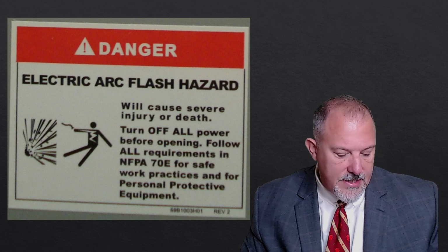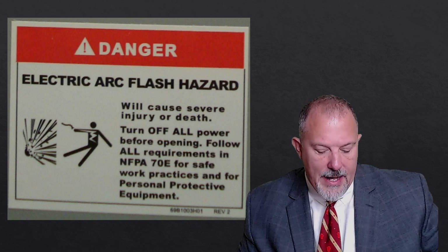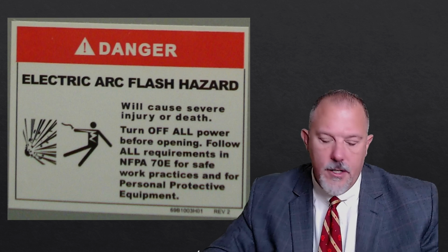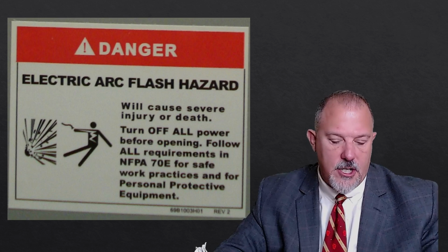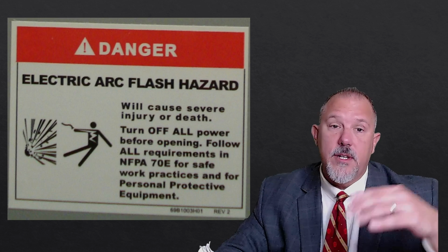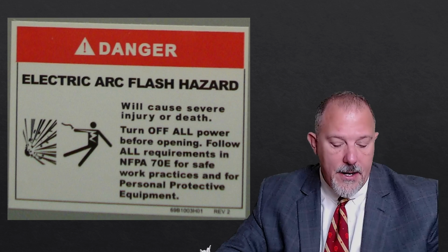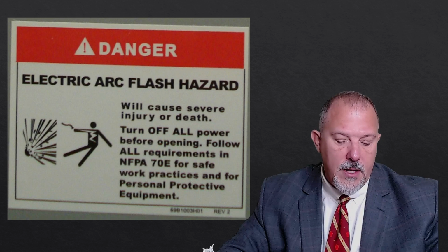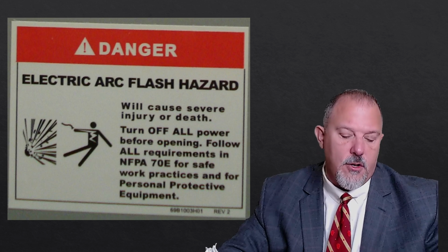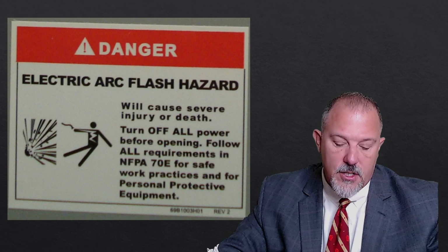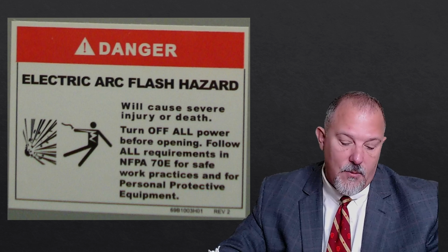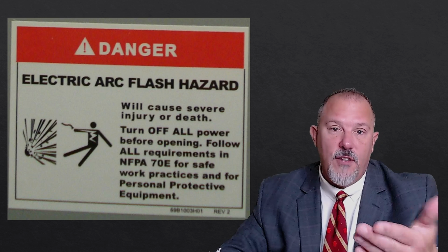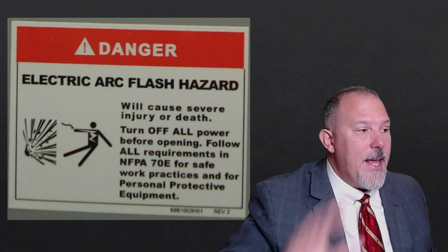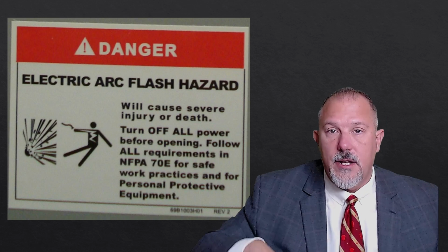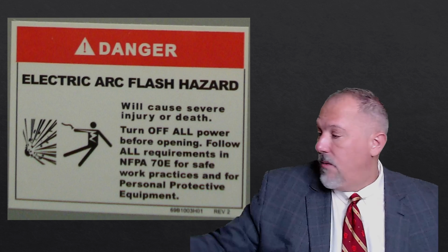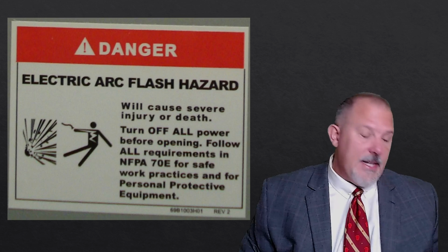So if you look at 110.16, you have an A, general requirements, which basically tells you some of the general information about how to apply that section. And B talks about service equipment. So at service equipment, you're going to be putting this label and that other label, possibly, or you're going to be putting the nominal system voltage, available fault current at the service overcurrent protective device, the clearing time of the service overcurrent protective device, and the date the label was applied. The exception is if you use a 70E label like the first one I showed you. Now, both of these labels that are in the 2020 code align with NFPA 70E.